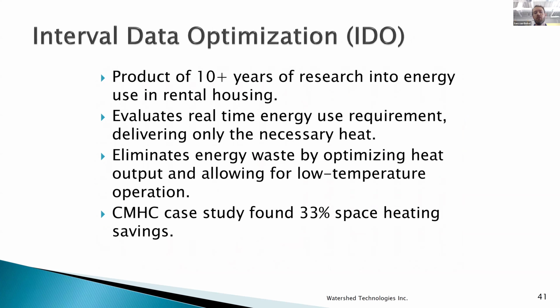So to address this issue of overheating in this particular building segment, we developed a process called interval data optimization, or IDO. This is based on 10-plus years of research into energy use in rental housing. It works by evaluating the real-time energy use of the building and then delivering only the necessary heat instead of overheating the building. It allows for lower temperature operation of the boiler plant in those shoulder seasons. And a CMHC case study found 33% space heating savings for a sample of buildings.